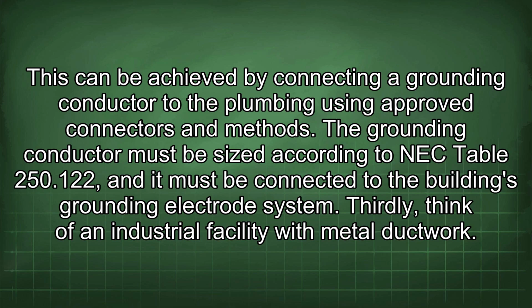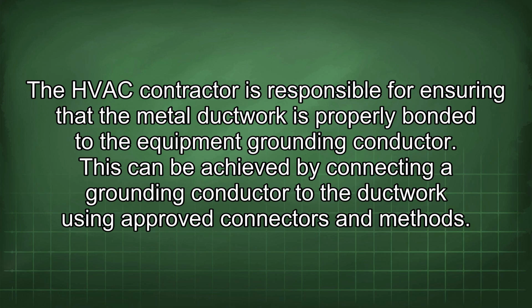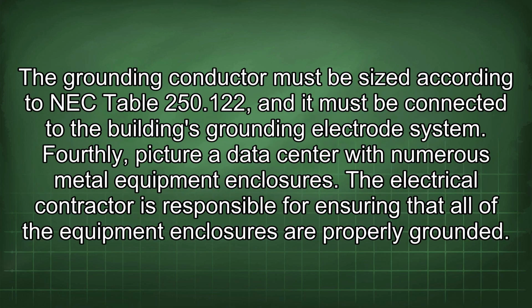Thirdly, think of an industrial facility with metal ductwork. The HVAC contractor is responsible for ensuring that the metal ductwork is properly bonded to the equipment grounding conductor. This can be achieved by connecting a grounding conductor to the ductwork using approved connectors and methods. The grounding conductor must be sized according to NEC Table 250.122, and it must be connected to the building's grounding electrode system.